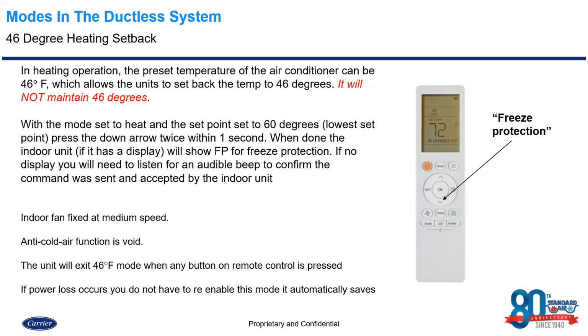Now, when the setback is initiated, you're going to hear an audible beep from the unit. If your unit has a digital display, it will display an FP for freeze protection. If it's a ducted style or a cassette style unit without a digital display or access to it, all you're going to listen for is an audible beep.